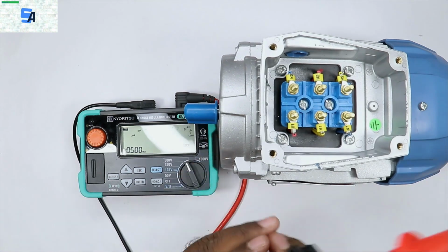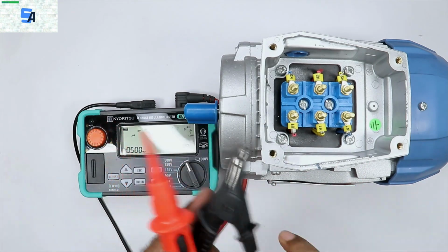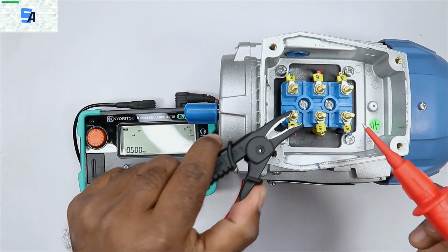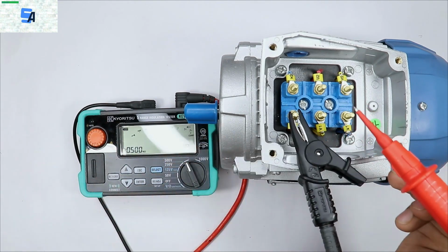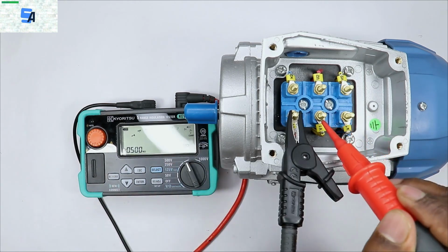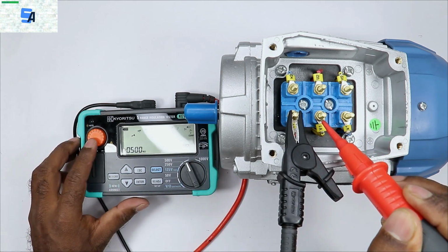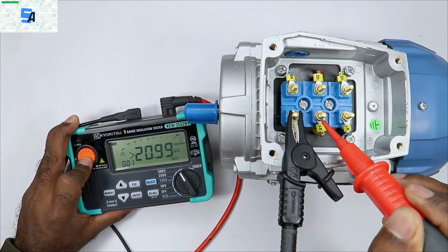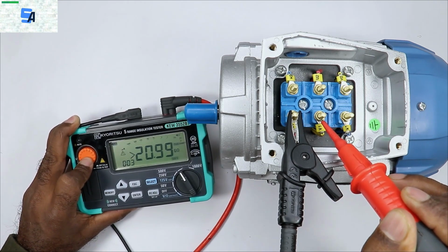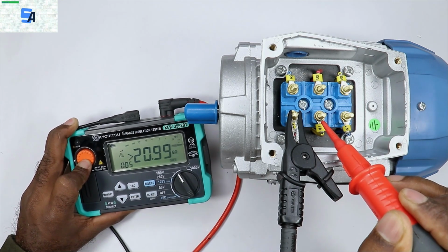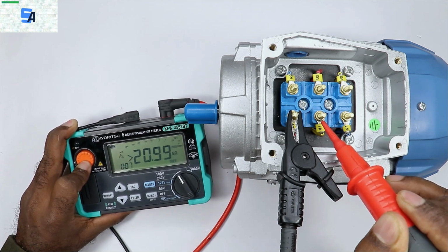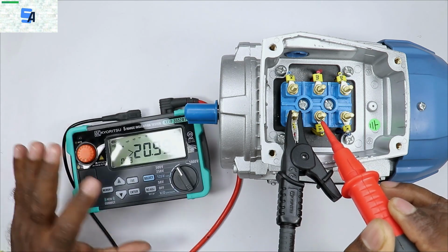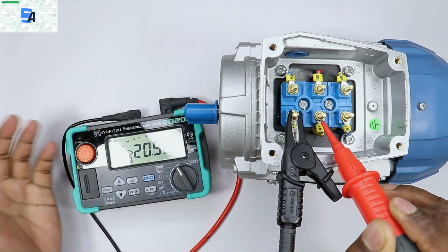After selecting 500 volts, take these probes and connect them with the winding. Connect one probe with U1 and the other probe with V1. After connecting, press this button. After pressing the button, we will get the IR value. You can see it is showing an IR value of 20.99 giga ohm. It means the megger I have, the maximum value of this megger is 20.99 giga ohm. So it is showing the whole maximum value.